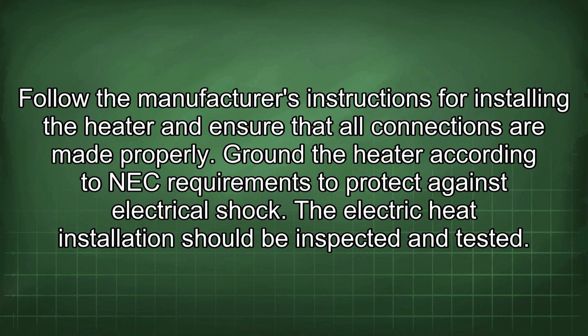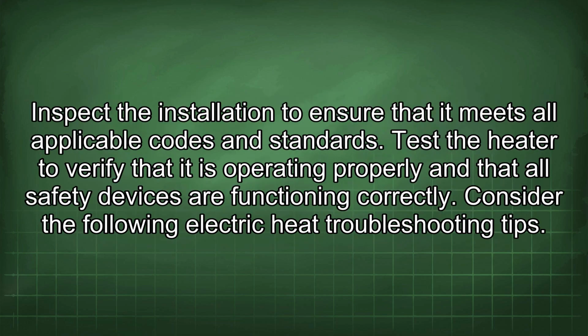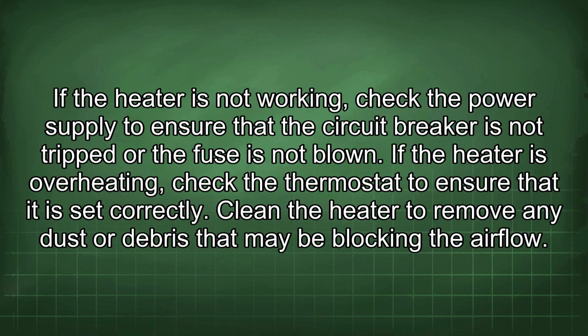The electric heat installation should be inspected and tested. Inspect the installation to ensure that it meets all applicable codes and standards. Test the heater to verify that it is operating properly and that all safety devices are functioning correctly. Consider the following electric heat troubleshooting tips. If the heater is not working, check the power supply to ensure that the circuit breaker is not tripped or the fuse is not blown.